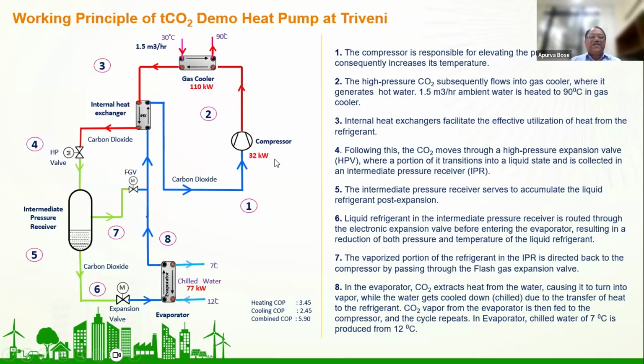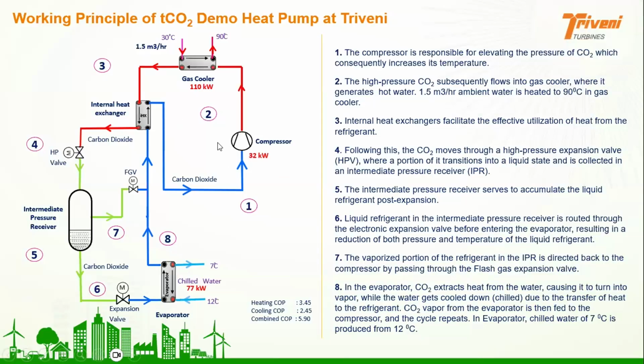I'm not sure whether my cursor is shown to you. Is it visible? Okay, I'm assuming it is visible. Yes. So the compressor is what we select based on the criteria given to us. After the compressor selection, the compressor compresses the CO2, which passes through the gas cooler, and here the temperature is quite high. I will talk about a specific example later, but here just to make you understand, this high temperature CO2 passes through the gas cooler, where we get the ambient temperature water, and it gives it back at 90 degrees Celsius or more.